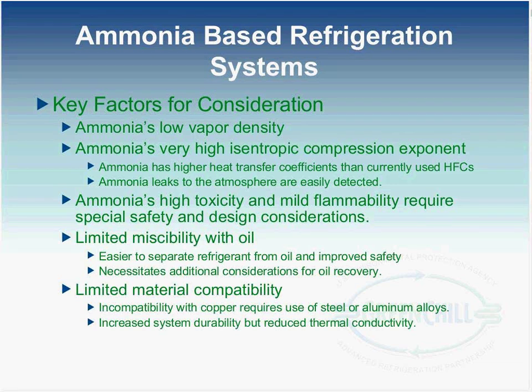Another disadvantage of ammonia is the high isentropic compression exponent, which is 1.31. When you compare with R404A, it is 1.14. This implies that the discharge gas temperature of ammonia is extremely high. If you are operating at a saturated suction of 14 and condensing at 90, you would see discharge gas temperatures of 270. The components are designed for that kind of temperature. The advantage you get is excellent heat reclaim capability.